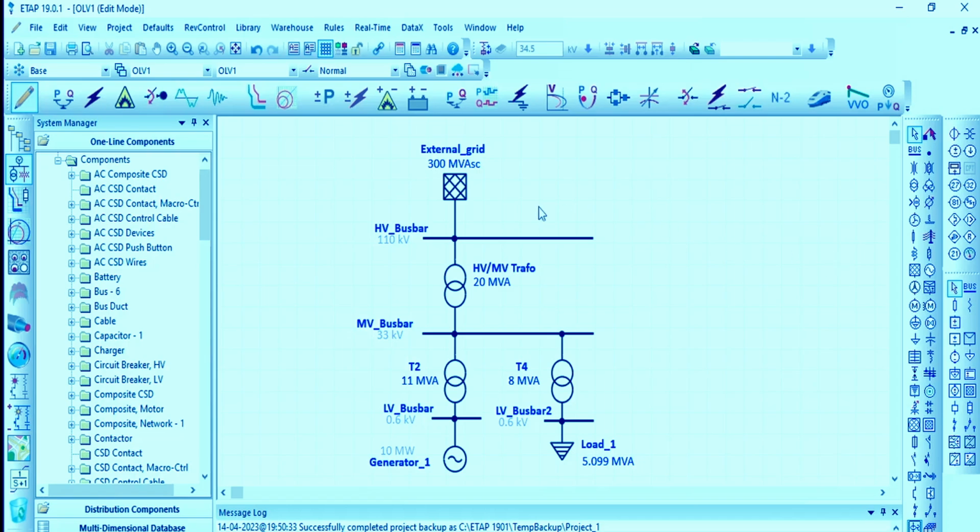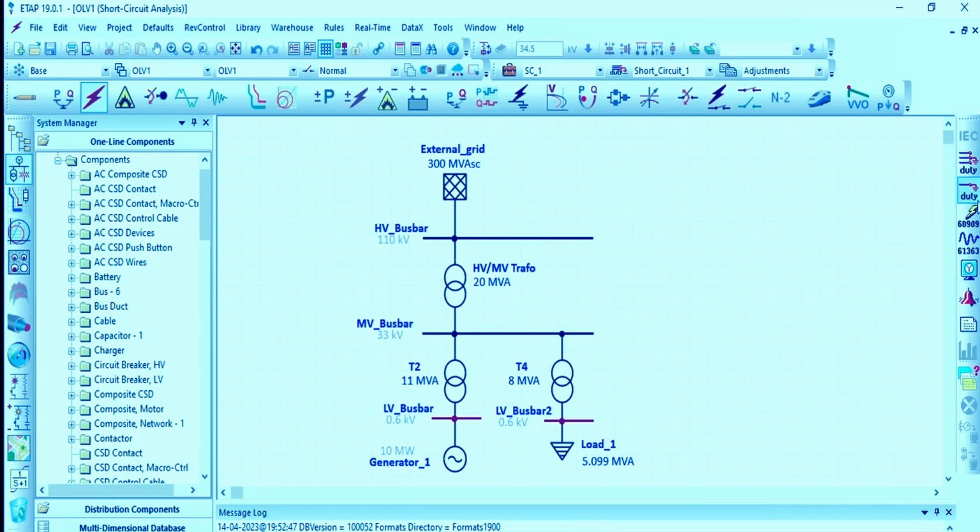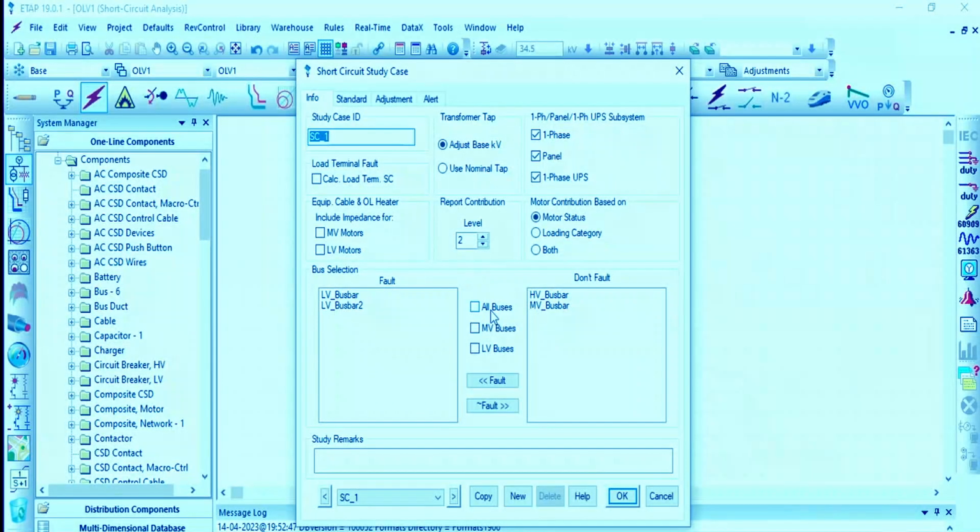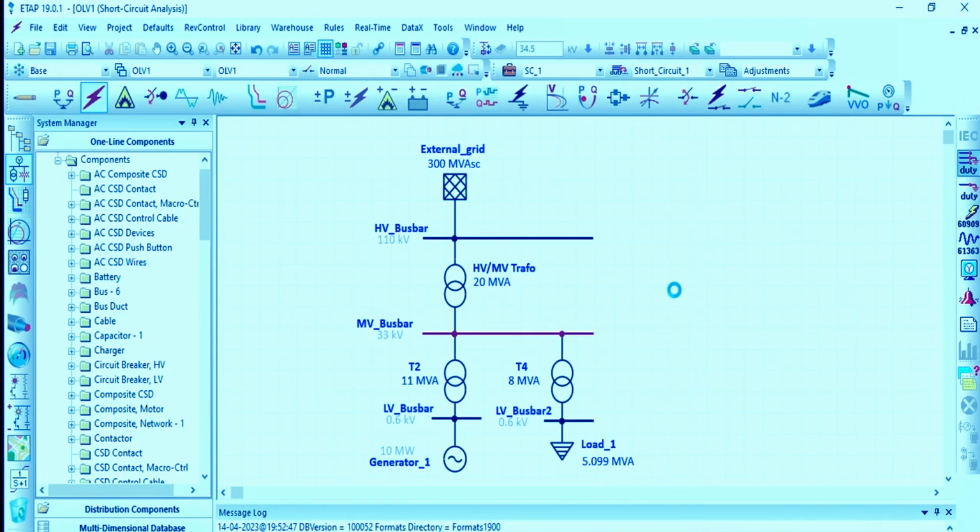Also, another thing that we can do, if we have very big networks, is split them. What it means by splitting is that here, for example, we'll perform it now. If we perform a short circuit again here, at the medium voltage, we can remove all the faults, and we perform a short circuit to the ground, and we see that it's at least 3.434 kiloamperes.